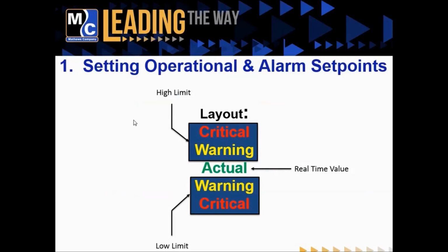So the first piece we want to look at is how to set alarm set points. I put a little diagram together here. You'll see a similar setup throughout the software for a lot of the alarm set points. The way we've organized this is with the actual value in the middle, displayed with green text. Above and below it, you'll have several different alarms associated with that value. We've organized it this way so you can see there's a warning alarm above your value and a critical alarm above your value, as well as a warning and critical alarm below that value.